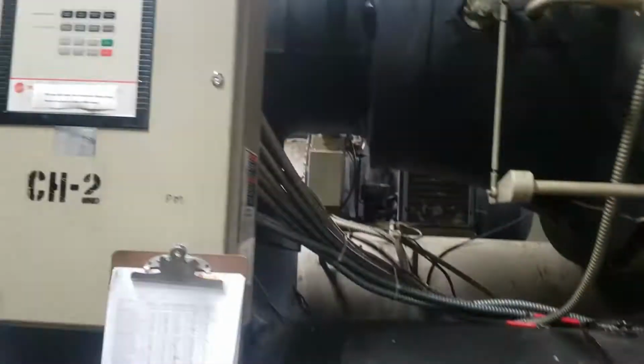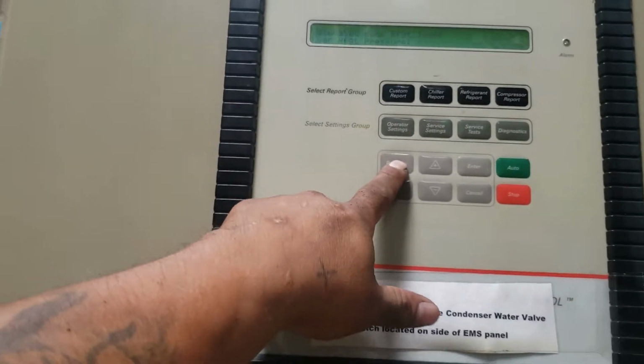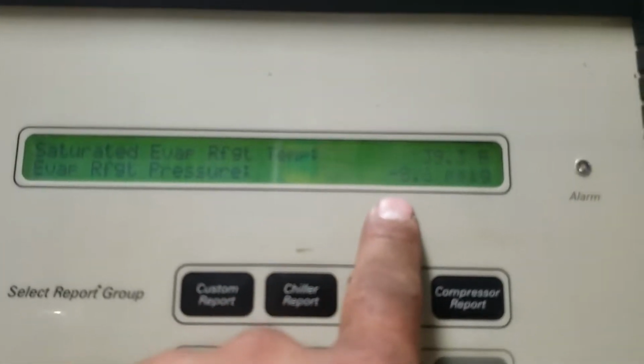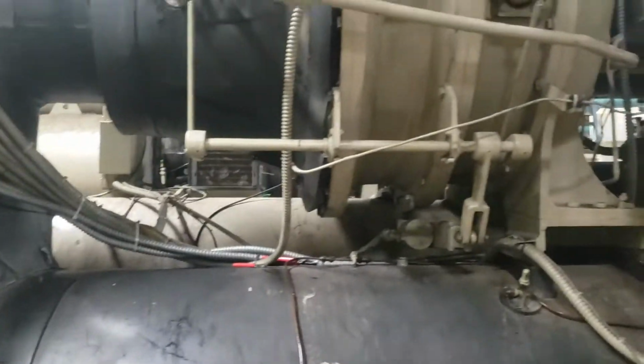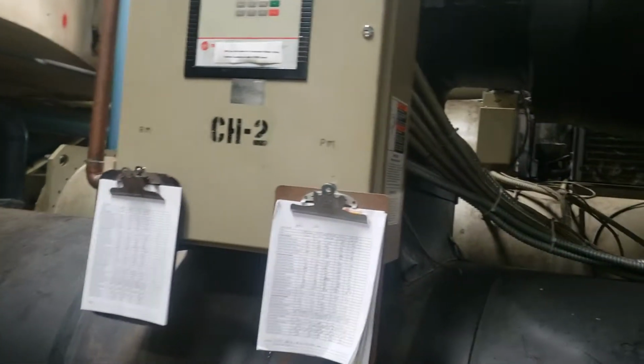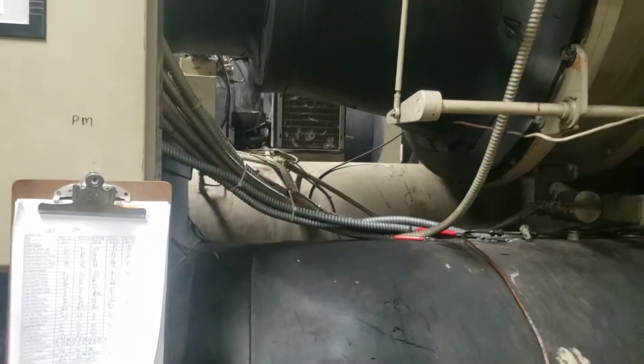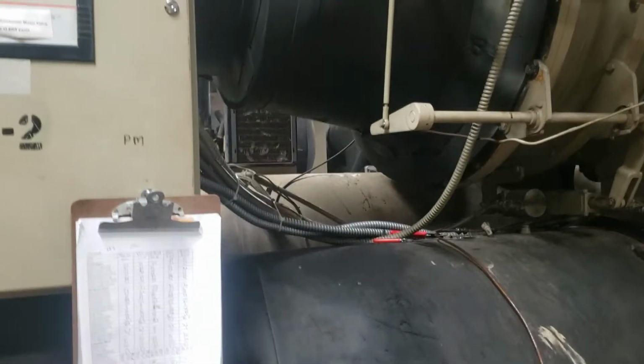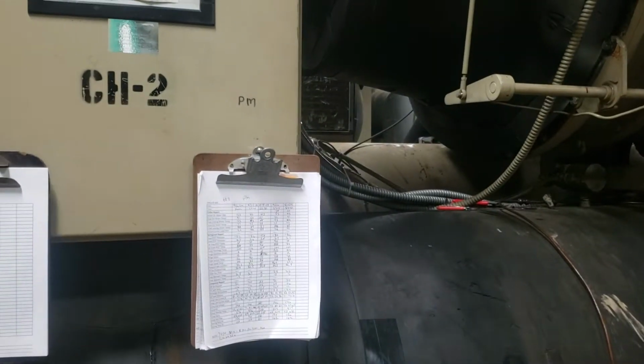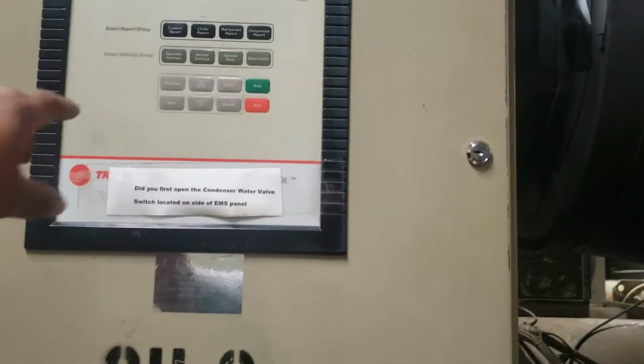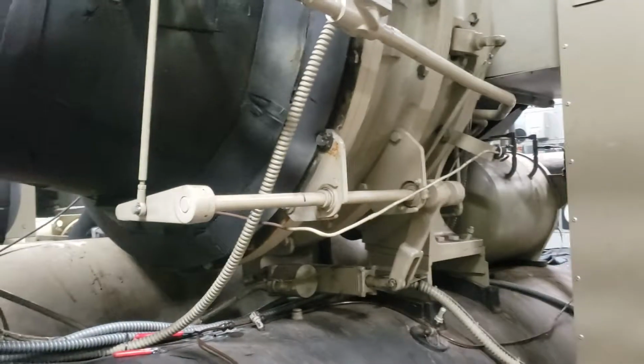The only thing that's under a vacuum when it's running is your evaporator, your low side. So if it's sucking in air when it's running, you know you have a leak somewhere on the low side. But let's say it only sucks in air when it's off. When it's off and it sucks in air, it could be from your low side or your high side, because the whole chiller is under a vacuum when it's off.